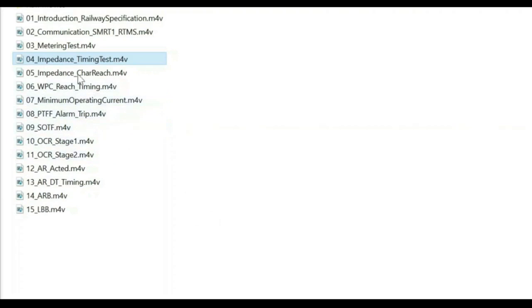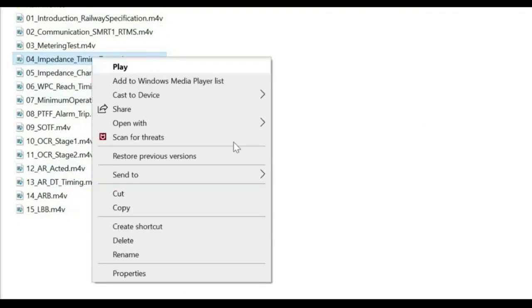How to test each and every protection function: impedance, characteristics, timing, reach test, minimum operation current, PT fuse fail, switch on to fault, overcurrent. Okay, I think few things, auto recloser, SOTF, these few things we did not see in the specification, or we did not read the specification fully. So we were not able to see this. So let me show you. Since you are having the video, you can directly understand what it is showing. Let me show you 3 things and maybe auto recloser. You can understand how we have tested it.